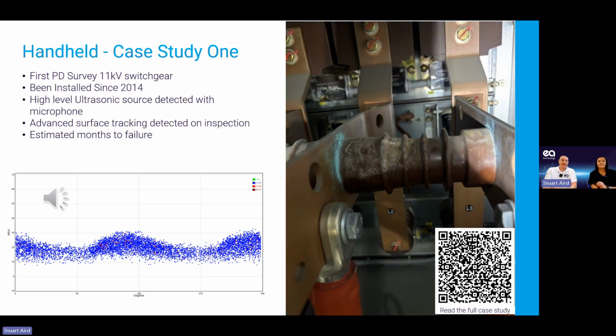Okay, so I've got a number of case studies here today, just to show you different ways of approaching things. The first few will be related to handheld surveys. As a team, we go out pretty much every day doing PD surveys at different customer sites, and they are quite often done annually or every 6 months, depending on the asset type. That gives you the benefit of being able to do quite a lot of assets with just one handheld product. So in this case, we've done a partial discharge survey at a site, and it's the first time we've ever been to this particular site. We picked up some high level surface related partial discharge, and I'll play the sound file for you.